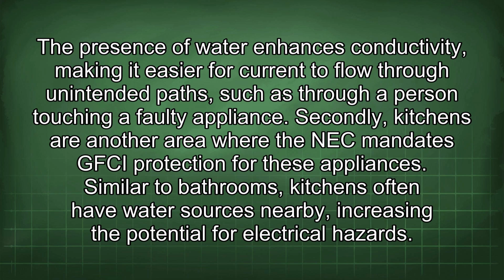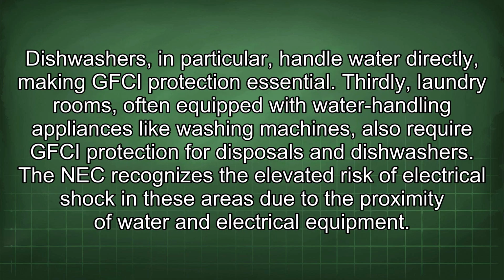The presence of water enhances conductivity, making it easier for current to flow through unintended paths, such as through a person touching a faulty appliance. Secondly, kitchens are another area where the NEC mandates GFCI protection for these appliances. Similar to bathrooms, kitchens often have water sources nearby, increasing the potential for electrical hazards. Dishwashers, in particular, handle water directly, making GFCI protection essential. Thirdly, laundry rooms, often equipped with water handling appliances like washing machines, also require GFCI protection for disposals and dishwashers.